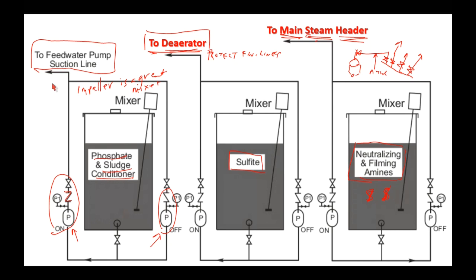I mean, that's one strategy for dealing with all kinds of pumps and compressors and all that kind of thing, is to rotate their activity, say, every month, and that way each piece of equipment gets even wear and tear, plus that the standby piece of equipment is actually functioning, ready to go. Okay, so each one of these has a couple of different pumps.